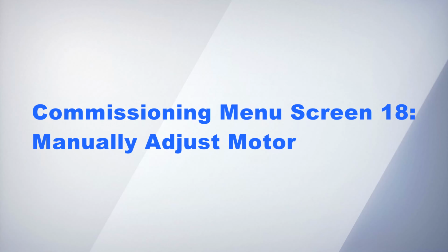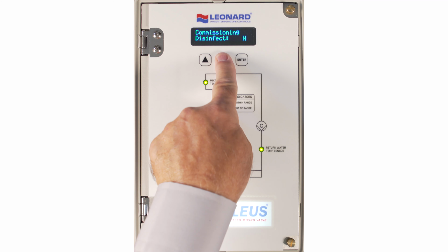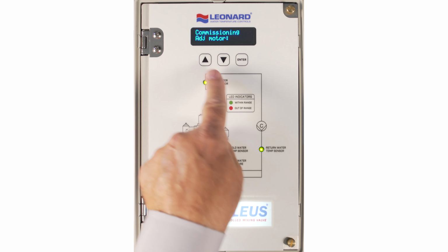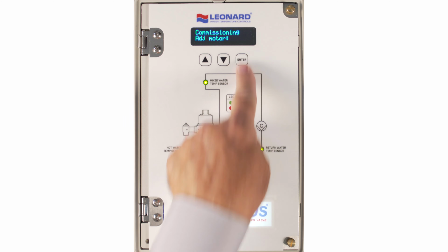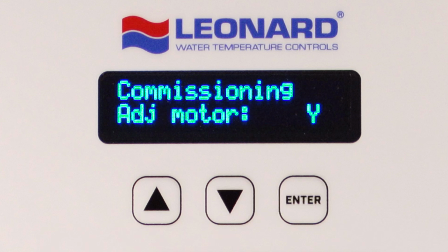Commissioning menu screen 18. Manually adjust motor. Pressing down 17 times displays Commissioning Adjust Motor, No or Yes. This feature allows the user to manually move the motor to ensure that it is mechanically connected, mechanically sound, and moving properly with no mechanical binding.